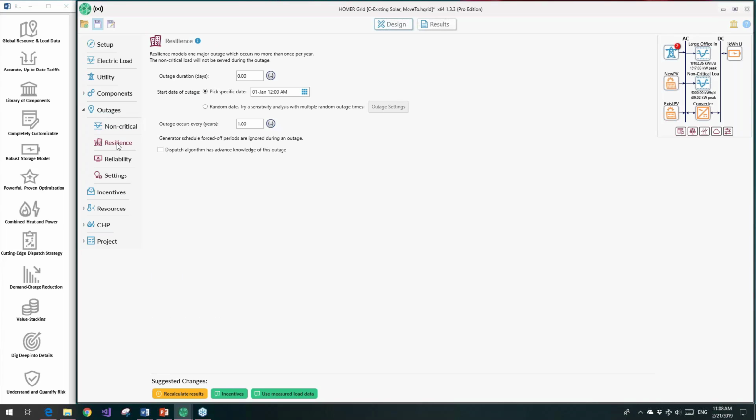So how you set up the outages is we have two different types of outages. We have the multi-day outages, which are just disasters. They happen once every many years and for multiple days. So we can say some disaster happens and it takes out the grid for 2 days. You can do more, but it may happen every 15 years.